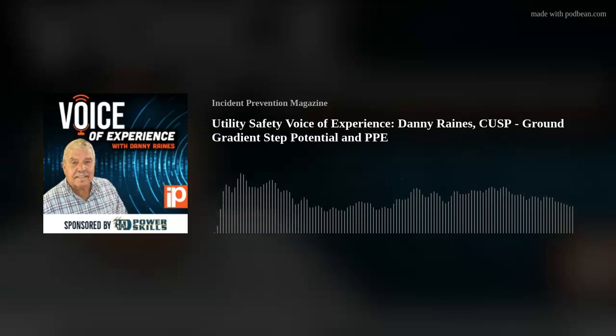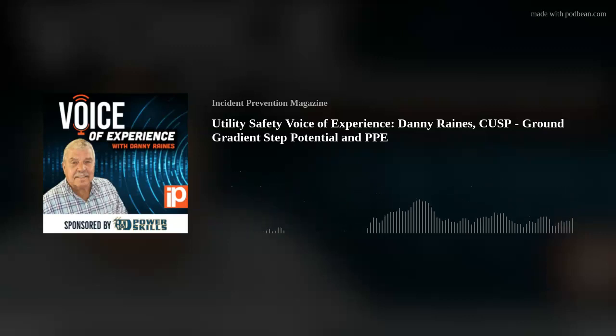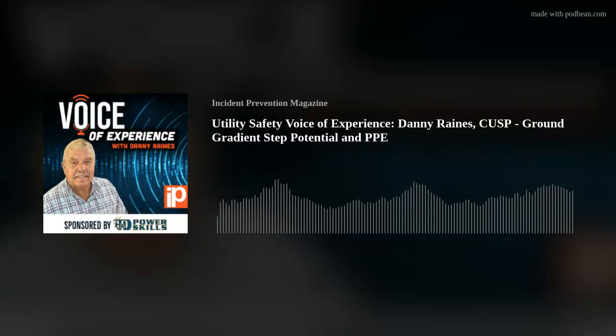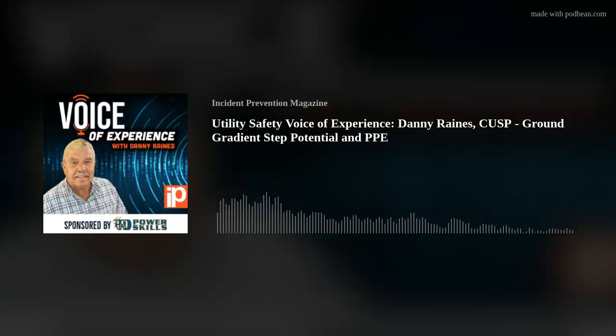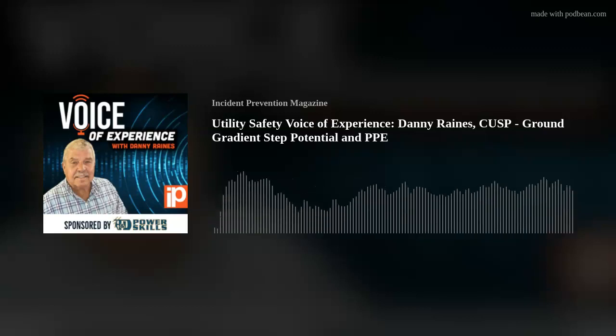But when you're standing in front of a meter base, everything is measured on about an 18-inch reach, okay? And here's another thing about an arc flash that I want to share with you, especially on these medium voltage or the 277/480 meter bases. We measure everything and test in the industry at 18 inches, arm's length. So what if you're looking up, with your face closer than 18 inches? That's not unusual, to look in to see the spades on a self-contained meter base, or if it's a bolt-in or whatever.